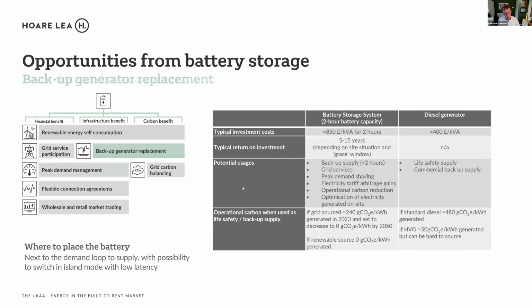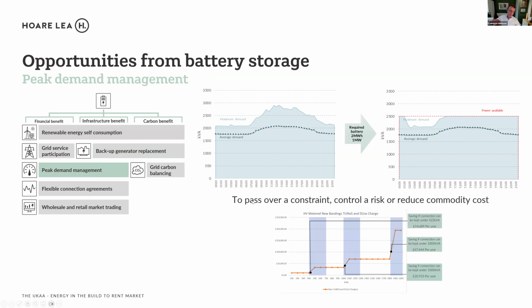It can also cover peak demand. If you have a constrained grid, and the grid can only give you 1 megawatt when you need 1.2 or 1.3 megawatts for your development, there can be a way to do that - if you can store the energy off peak and then play it back to stop your development from going over that peak. Preventing reinforcement may not save too much in capital cable reinforcement, but you could save significant time in delivery. Going back to what I said around 2030 being not unusual for connection times, 2035 for grid capacity connections - this is a way around it.